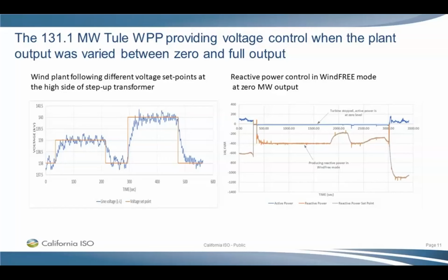On the day when we tested this plant, the voltage at the high side of that transformer was high, so we could only buck the voltages, and we bucked it. Then right about the middle of the curve, you see we were able to increase and get reactive power out of that plant. This is very interesting in that even though the wind's not blowing, you can get voltage support from a wind plant.